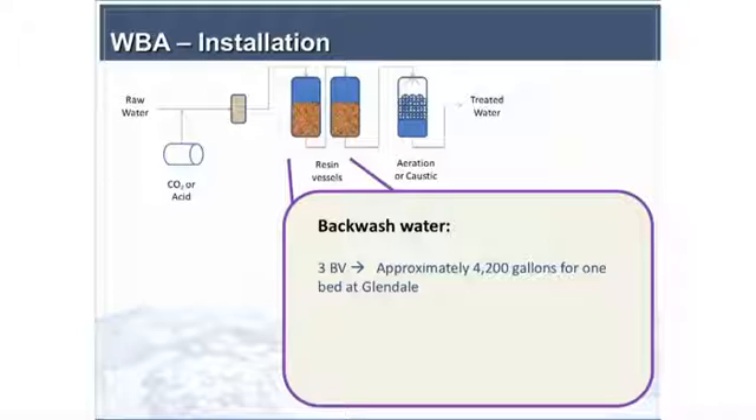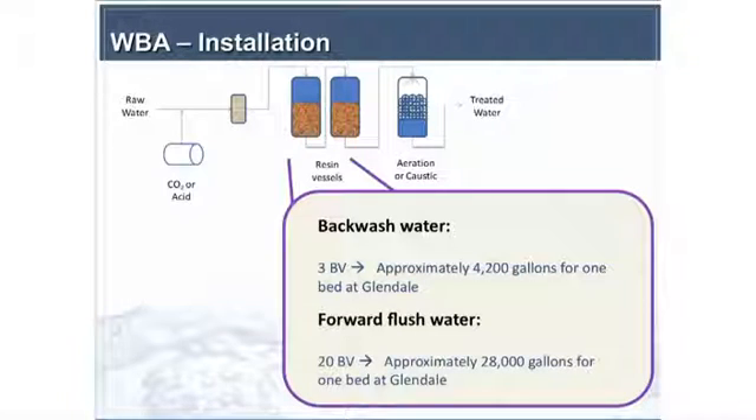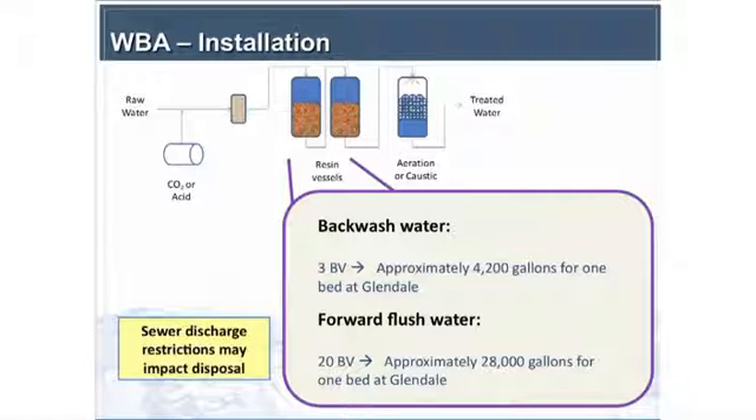The backwash water is also a key consideration for weak-base resin — needing the ability to backwash and fluff the bed initially, and then forward flush water before service. There's a significant quantity of water generated, and there may be sewer discharge restrictions. For Glendale in this particular case, they're limited by formaldehyde — they have to have non-detect levels of formaldehyde in their discharge, which is a significant issue.